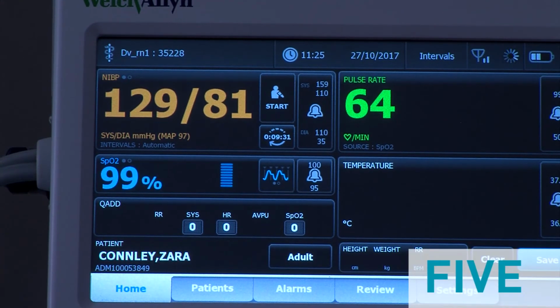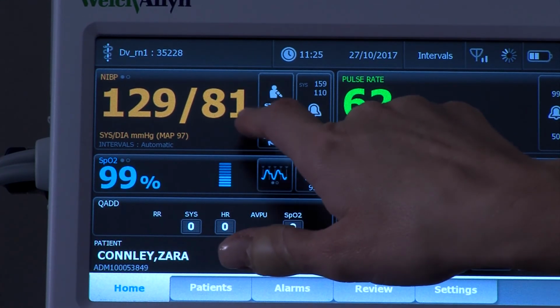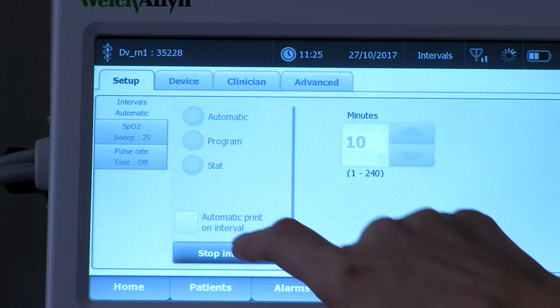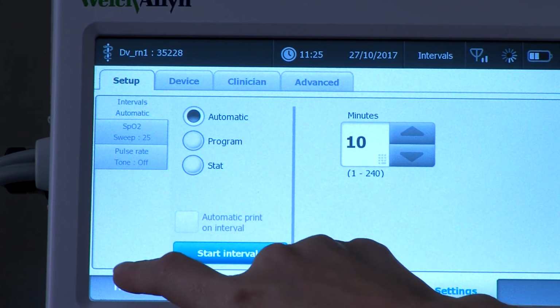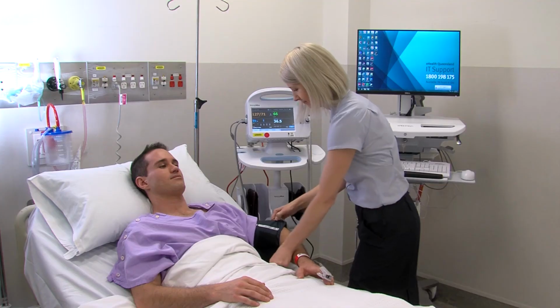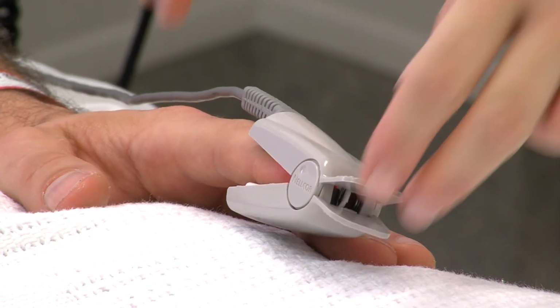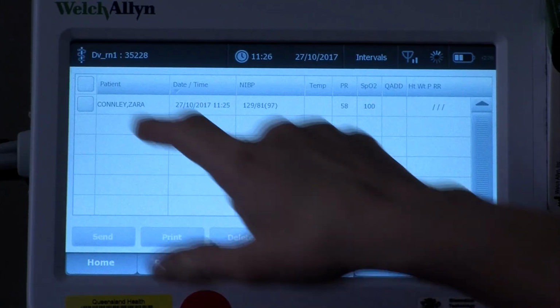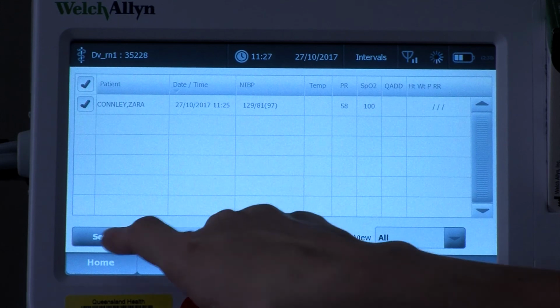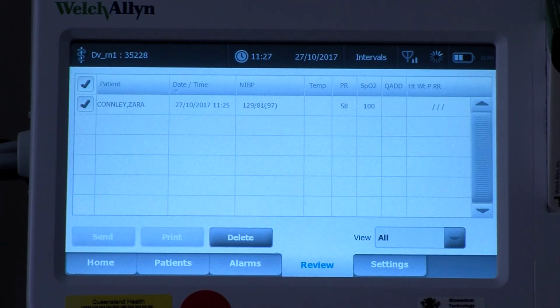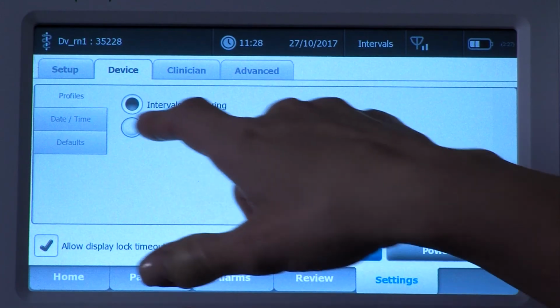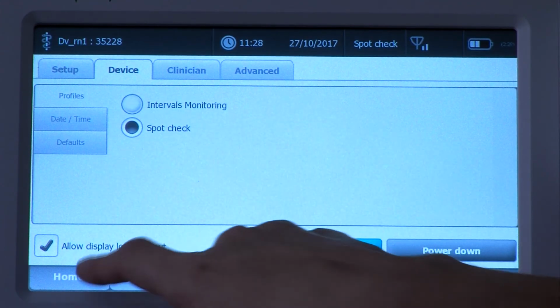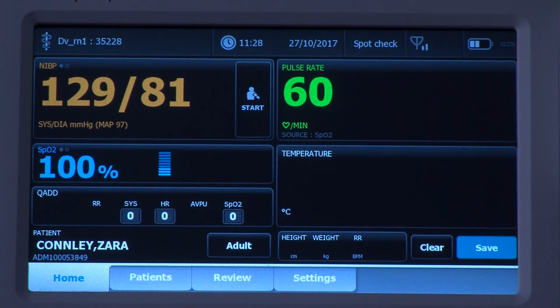5. Once the interval observations are no longer required, touch the clock icon in the BP area, touch stop intervals, detach the cuff and oxygen SATS probe from the patient and send any remaining results. Finally, return the monitor to spot check mode, press save to clear patient and clinician data.